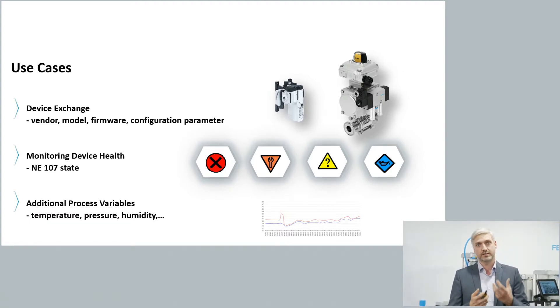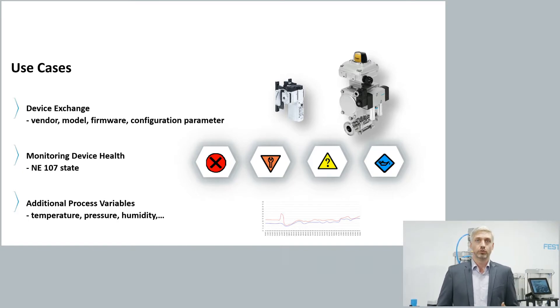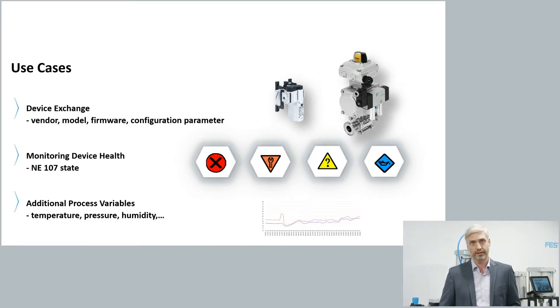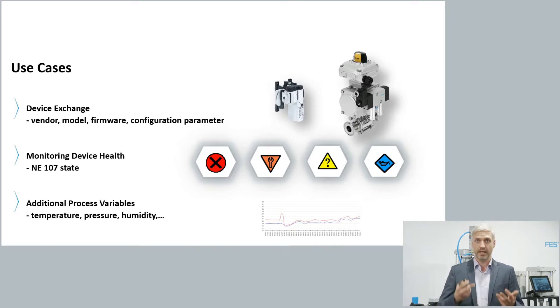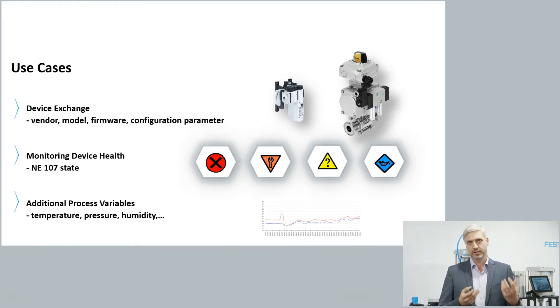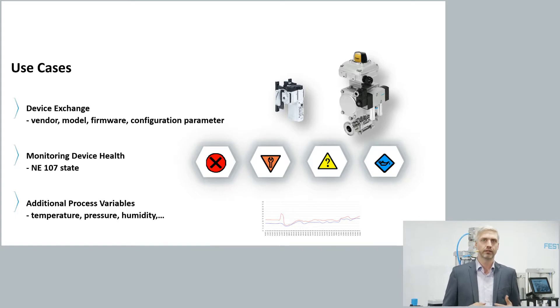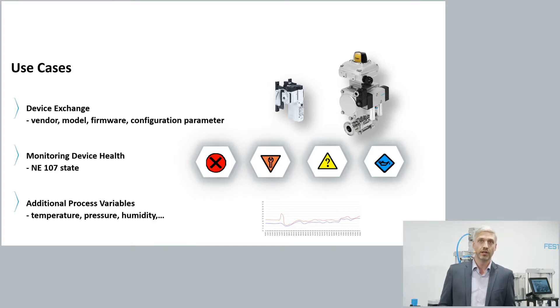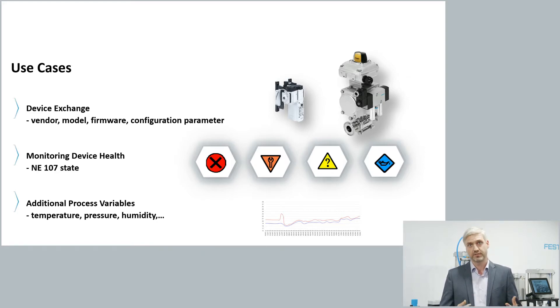For device exchange, all the information needed to swap a device — including configuration parameters, vendor type, firmware version, software revision, and so on — is part of the NOA information model. This ensures 100% correct device configuration, and you can pre-configure the replacement before the exchange. The second use case is device health: always having a clear picture of the status of all devices in your plant, following the NE 107 NAMUR recommendation for displaying asset health — whether the asset is in good shape, needs maintenance, is in manual mode, and so forth.